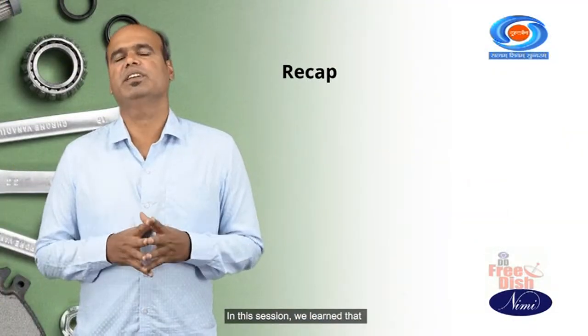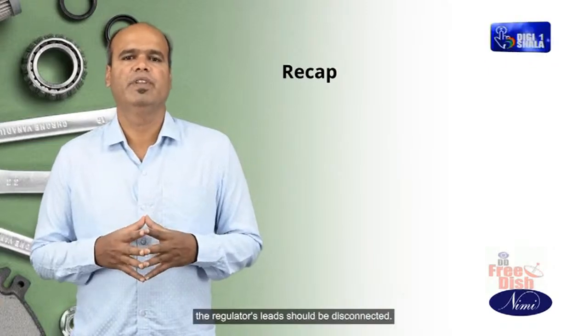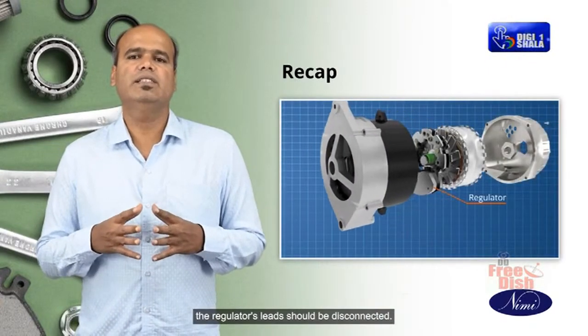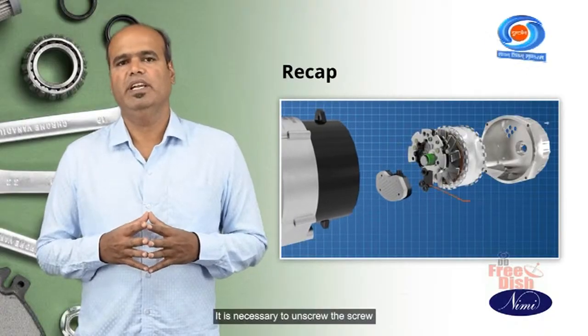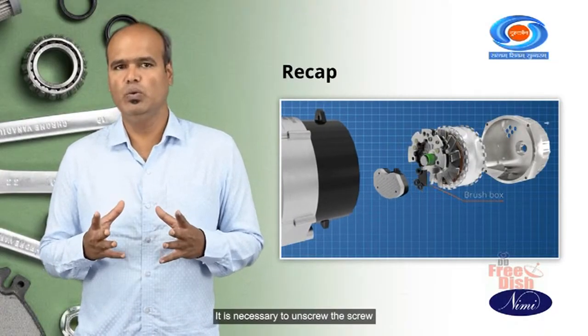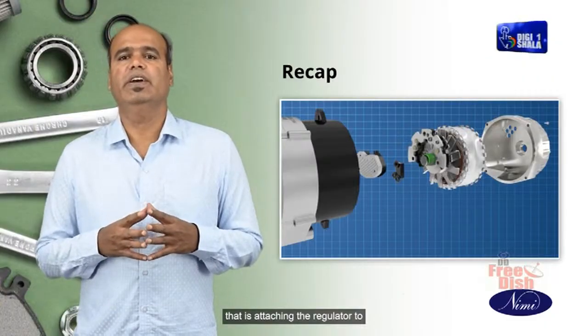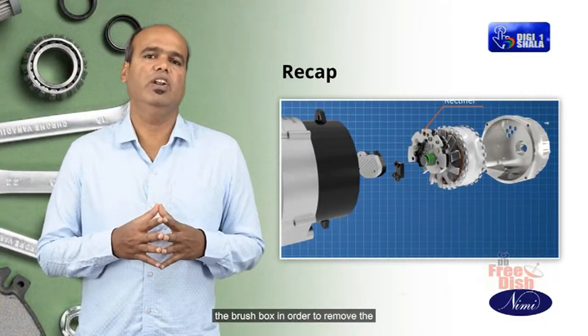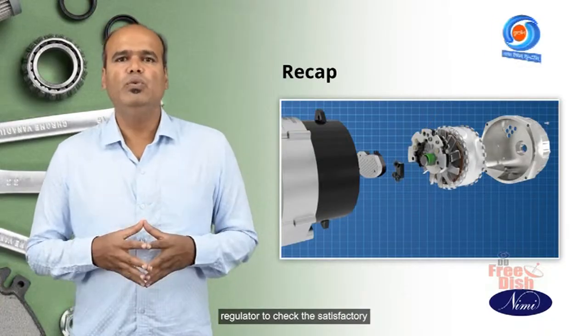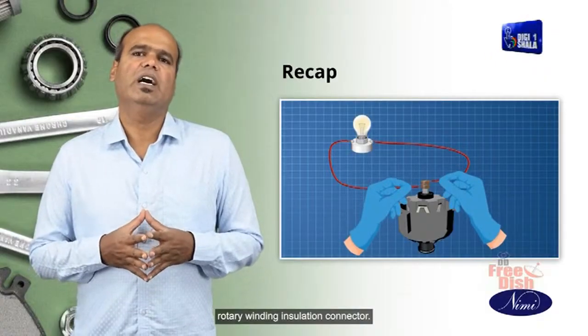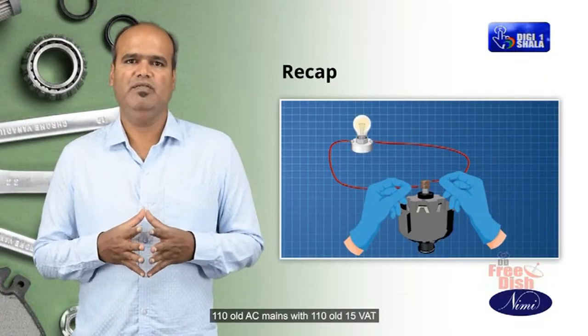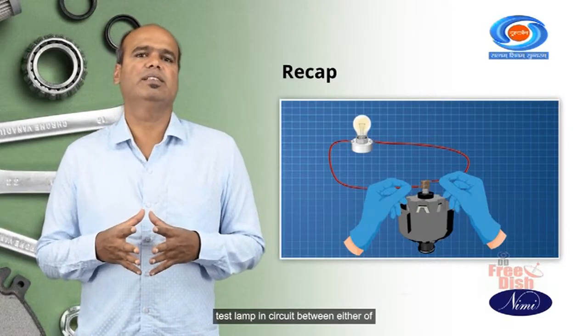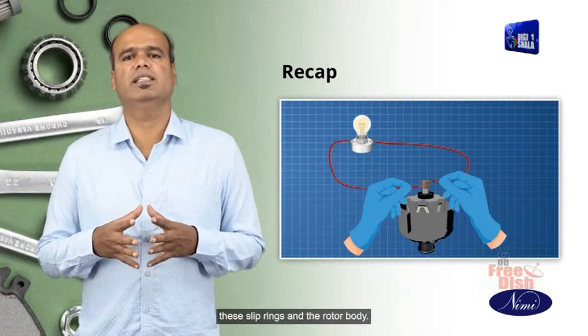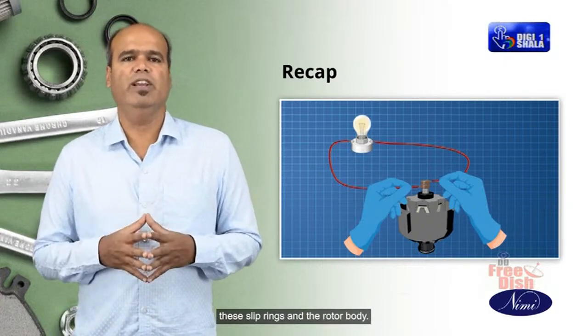Let's recap this session. In this session, we learned that the regulator's leads should be disconnected. It is necessary to unscrew the screw that is attaching the regulator to the brush box in order to remove the regulator. To check the satisfactory rotary winding insulation, connect a 110 volt AC mains with a 110 volt 15 watt test lamp in circuit between either of the slip rings and the rotor body.